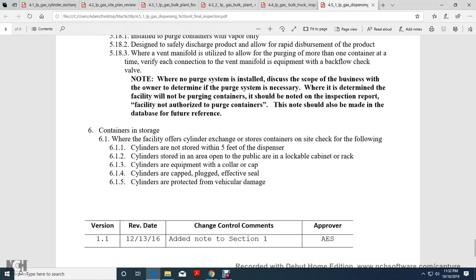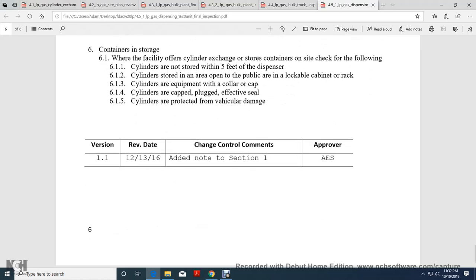Container Storage: If the facility offers cylinder exchange storage, check containers at the site for the following: Cylinders are not stored within 5 feet of the dispenser. Cylinders stored in an area open to the public must be in a lockable cabinet or rack. Cylinders must be equipped with a collar, cap, or plug in an effective seal. Inspect cylinders for vehicle damage.